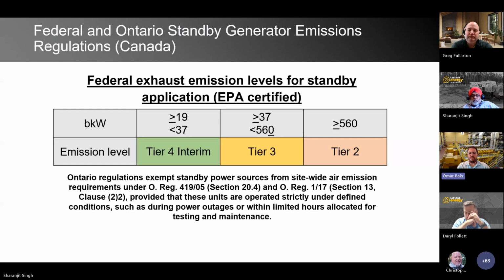This is the federal emission standards for standby diesel generators. Generally they have to be EPA certified, and this depends on the engine size, not the power the generator generates. So we look at the brake power coming from the engine, and that brake power determines the tier level the engine will carry. For example, any engine with brake power between 19 and 37 will have a Tier 4 interim certification. Any generator with brake power between 37 and 560 will carry a Tier 3 EPA certification. Anything above 560 will carry a Tier 2 certification.